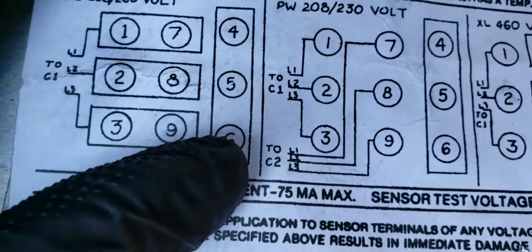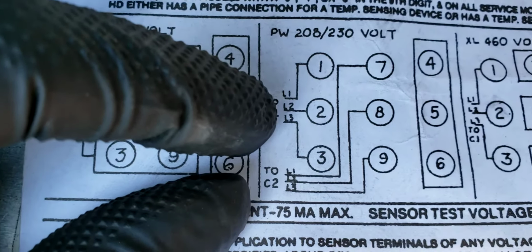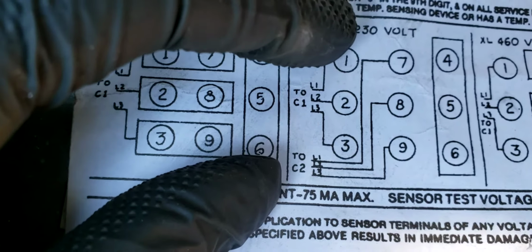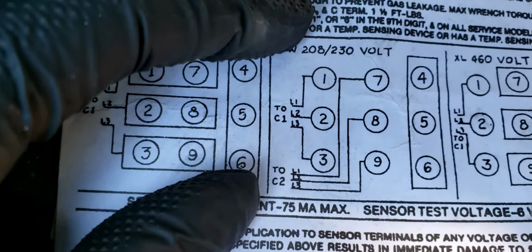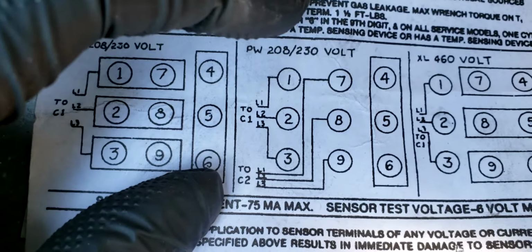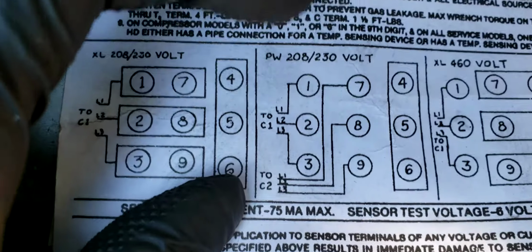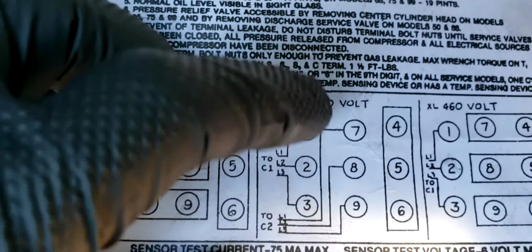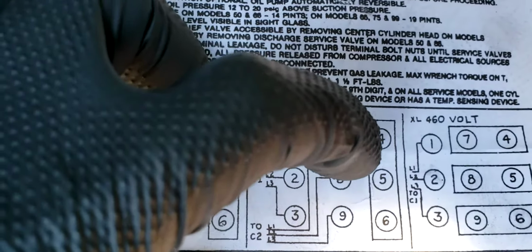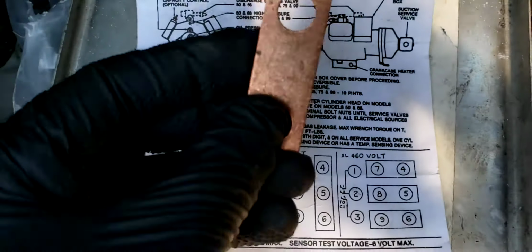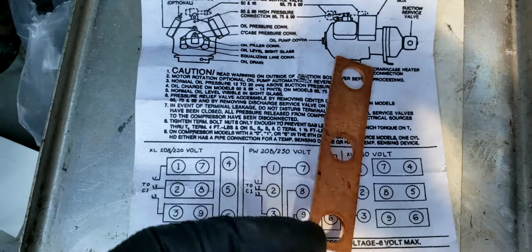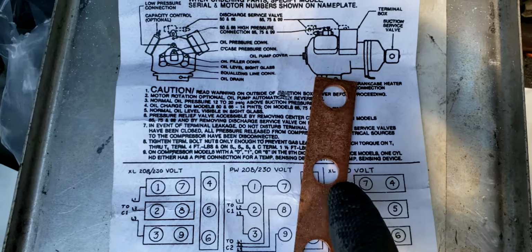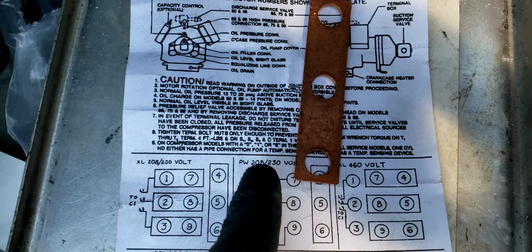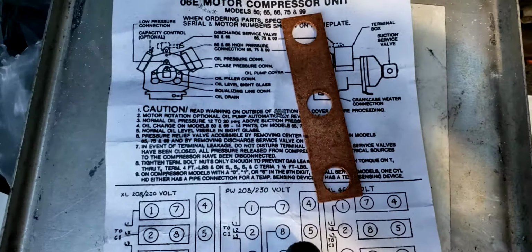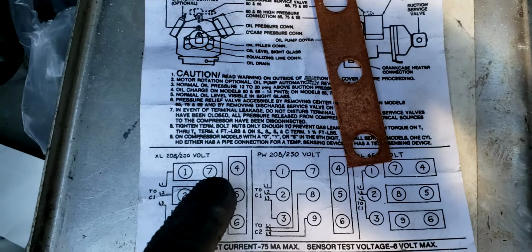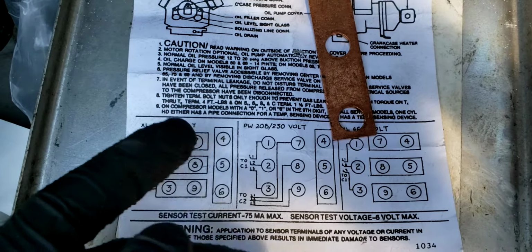If you see here, they tell you C1 or contactor number 1 goes to 1, 2, and 3. So those 3 wires off of contactor number 1 will go to terminal 1, 2, and 3, right? And then the other 3 wires from contactor number 2 would go to 7, 8, and 9. And all you'll be using in the part winding setup is this one piece of shunt right here. That's all you use. This will cover 3 of your terminals, which is 4, 5, and 6. The other remaining 6 terminals will be connected to your contactors.